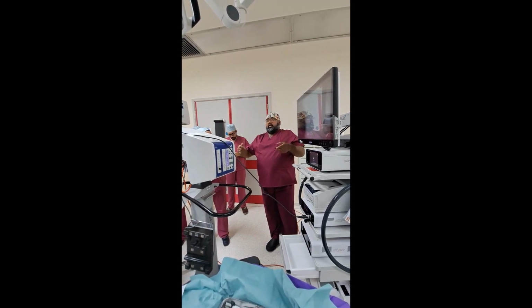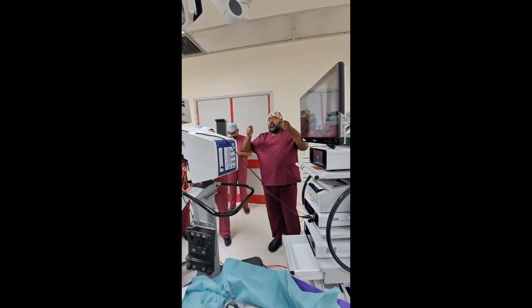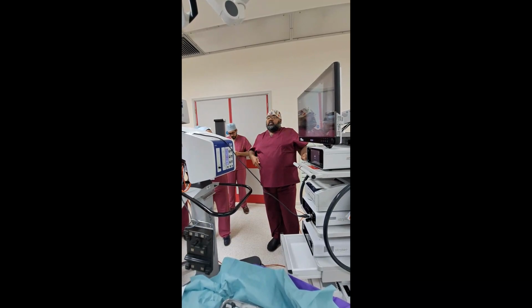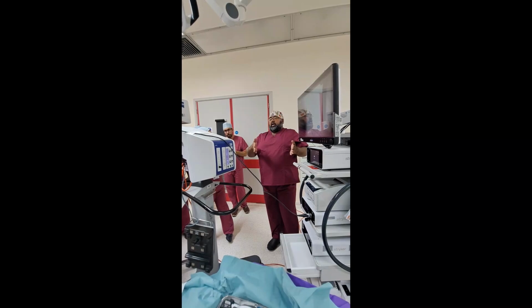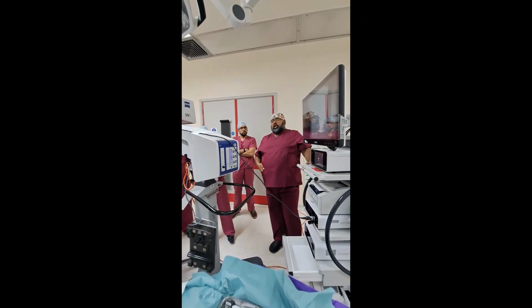And like you say, if you put it fixed, you can't get it wrong. You just put it out until it focuses, then once you go too far, it will defocus again. So that is the giveaway for fixing it back to where it is. Because you get into the scenario where the laser's set in the wrong place, or the microscope, and you end up just kind of cross-covering. And then you end up in the wrong place, wrong depth, and so on.